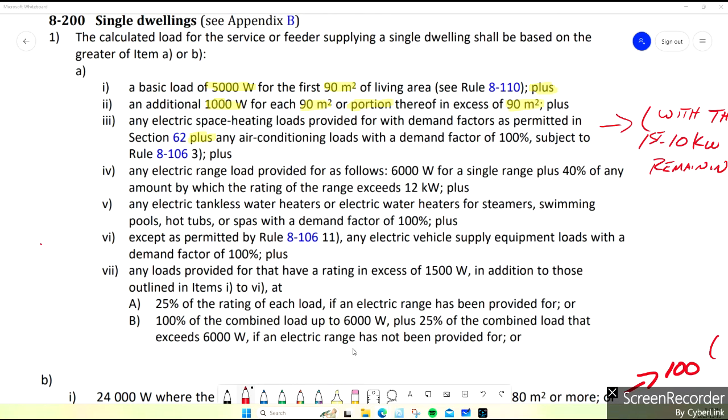So I'm not sure about the rest of Canada, but in Ontario, we typically put a receptacle in for an electric range regardless if there is going to be a gas stove or not. Well, obviously, if there's not, there would be an electric range. But if the client's going to put a gas stove in, well, I'm still going to be putting in a receptacle for this, so I would still be applying 7A here.